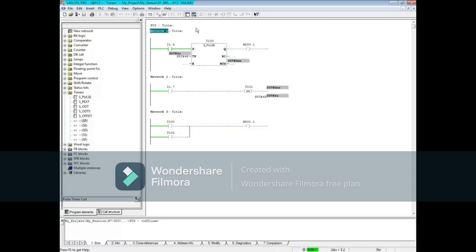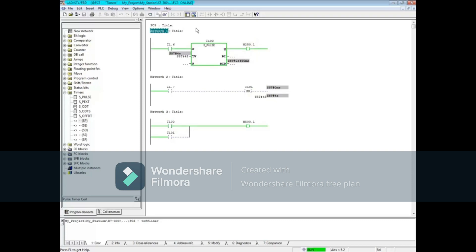Transition input 1.6 to false and then to true again. If the input goes false before the timer times out, the timer will stop timing and the coil goes to 0. Each time the input transitions, the timer automatically restarts.